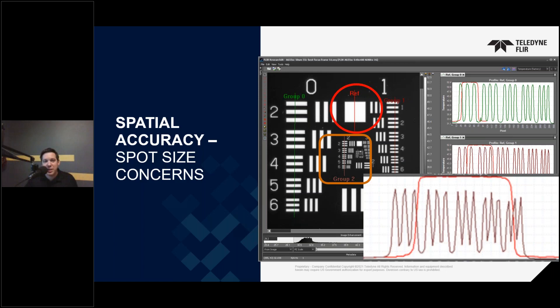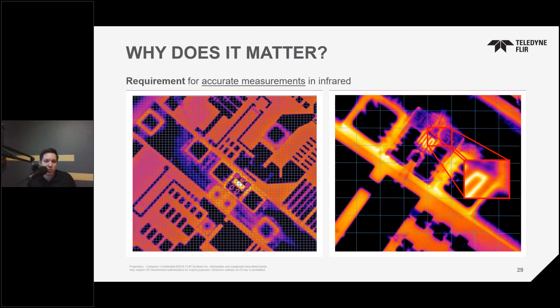So now we're back to why this all matters. In this image, we were unable to read an accurate temperature because we didn't have the required level of spatial resolution to fill enough pixels with the target component. Our spatial resolution was so poor that we were capturing the thermal data from everything in the pixel and averaging it out. Not only was our pixel data inaccurate, but there was absolutely no way we were going to be able to read that component. Let's say we had better resolution — but how much better does it have to be?